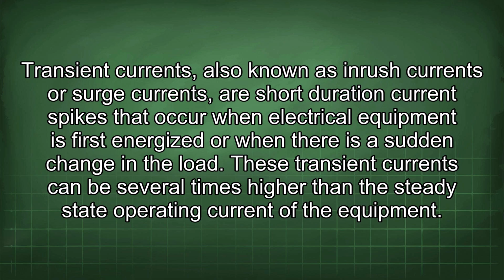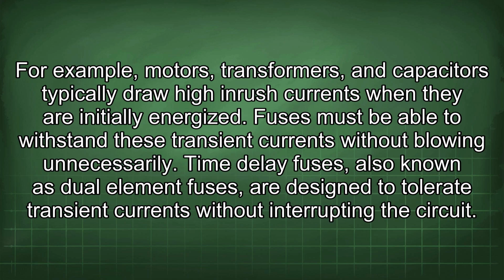Transient currents, also known as inrush currents or surge currents, are short-duration current spikes that occur when electrical equipment is first energized or when there is a sudden change in the load. These transient currents can be several times higher than the steady-state operating current of the equipment. For example, motors, transformers, and capacitors typically draw high inrush currents when they are initially energized. Fuses must be able to withstand these transient currents without blowing unnecessarily.